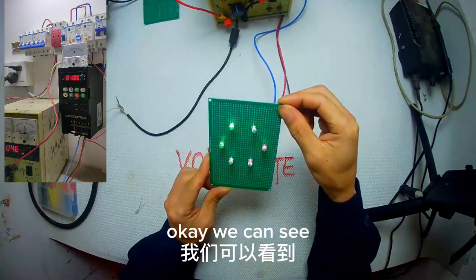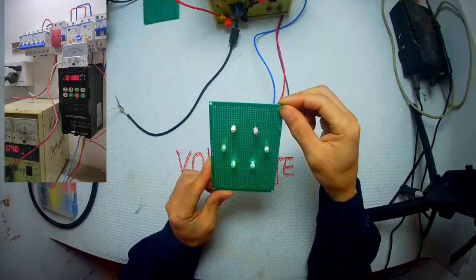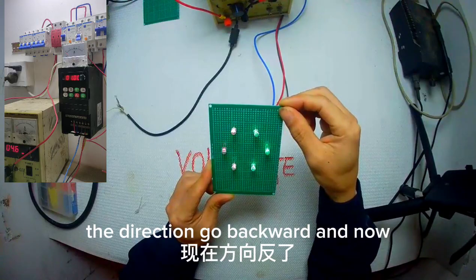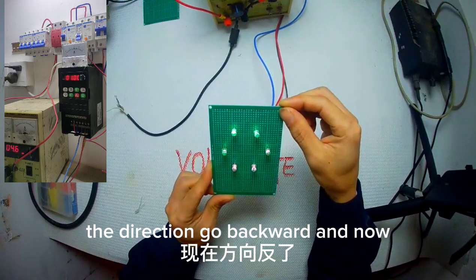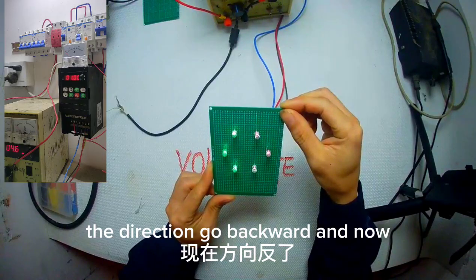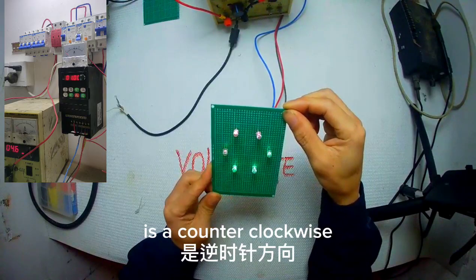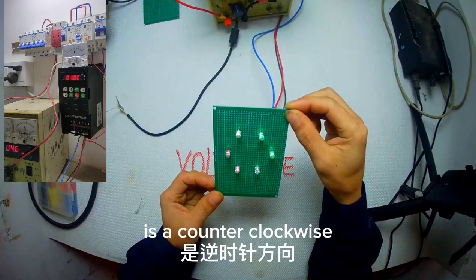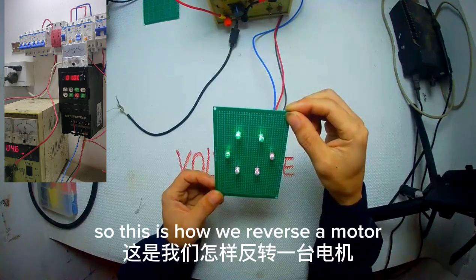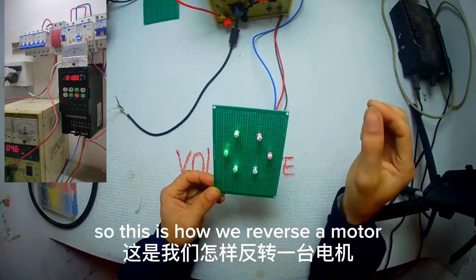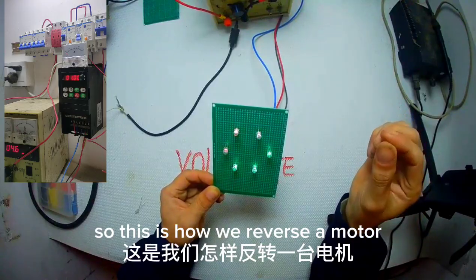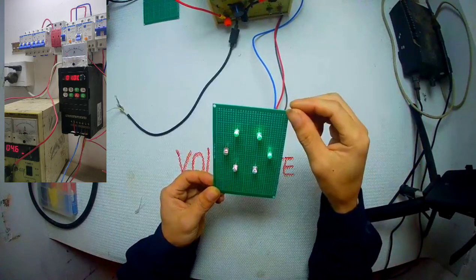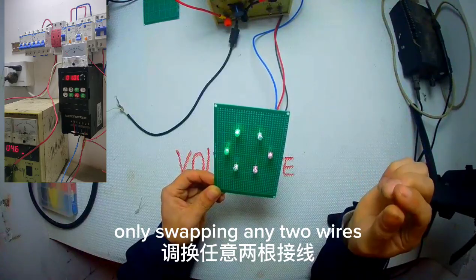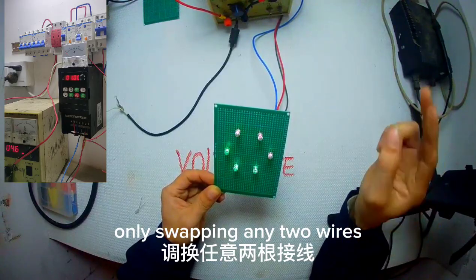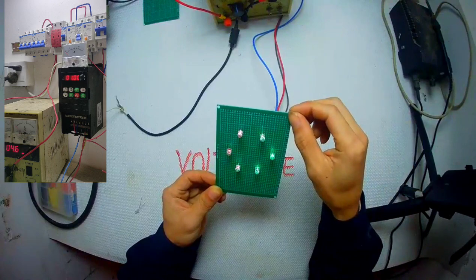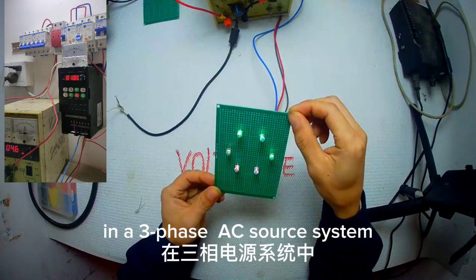Okay, we can see the direction goes backward, and now it is counterclockwise. So this is how we reverse a motor: only by swapping any two wires in a three-phase AC source system.